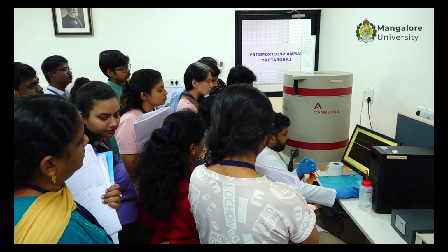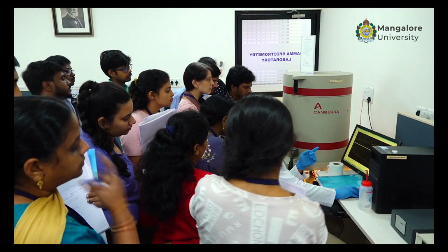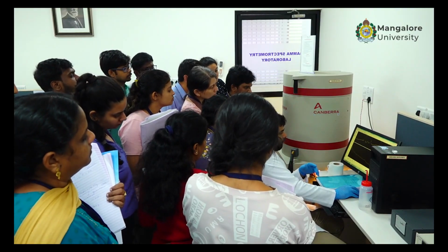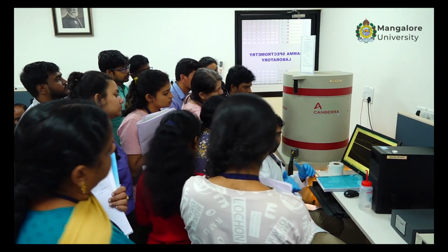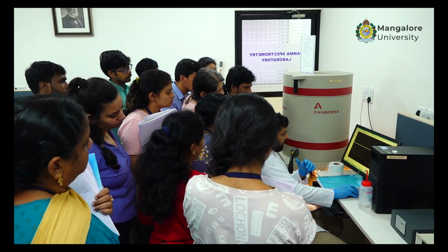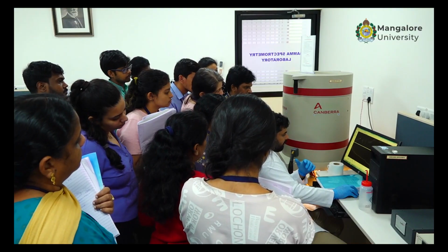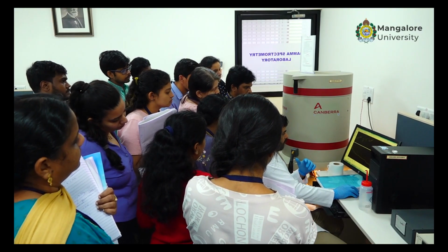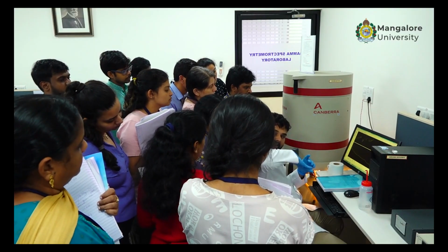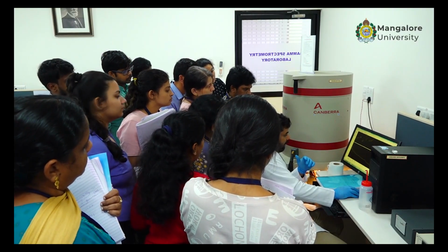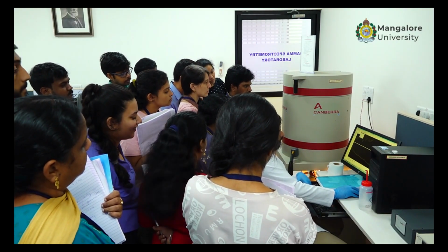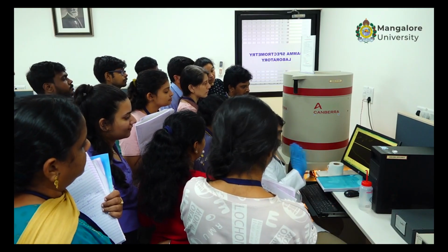So each channel, you can see this channel has 988 counts, and it goes higher, gets to the peak and then drops, correct? So you want to put two markers. You have already seen how to mark, right? Here I make it as big as possible and check the bottommost part. I have to put the point where the peak is just ending and the next peak starts. So I can put it over here, and then I'll go to display ROI, add ROI.